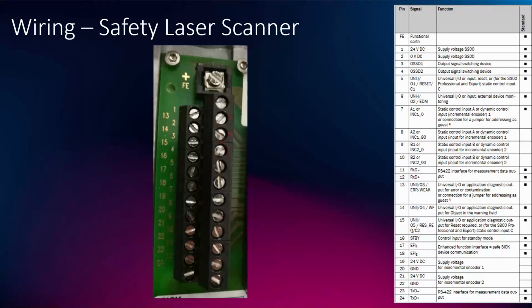We will now take a look at the connection types found on a specific laser scanner. This is the wiring terminal that is found on the SICK S300 standard series laser scanner, and we will take a look at the connection pins one by one. The pins number 1 and 2 are the main power inputs of the safety device. This is where you connect 24 volts DC in order to power it. This voltage can commonly be found on the robot controller's external interface, or an external power source may be used.